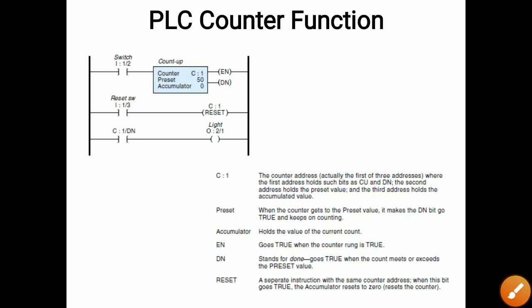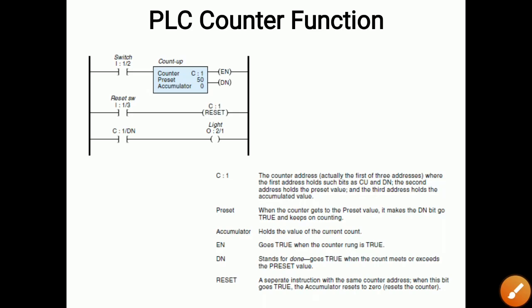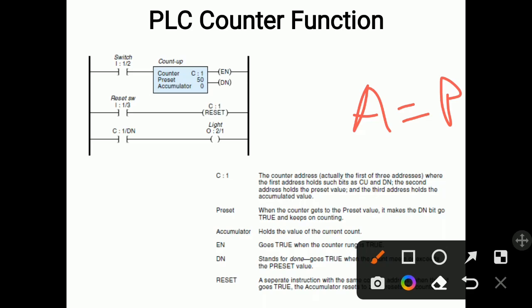The preset is the value at which the counter makes the DN bit true and keeps counting. The accumulator holds the value of the current count. EN goes true when the counter rung is true. When the accumulated value equals the preset value, DN activates, the DN contact closes, and the light turns on. If you want to reset the counter, close the reset contact and the counter will reset.